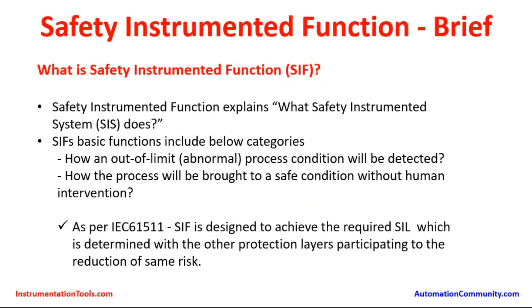What is Safety Instrumented Function? Safety Instrumented Function explains what a Safety Instrumented System does. SIF basic functions include: how an out-of-limit or abnormal process condition will be detected, and how the process will be brought to a safe condition without any human intervention. As per IEC 61511, this is the international standard, SIF is designed to achieve the required SIL, which is determined with the other protection layers participating in the reduction of the same risk.